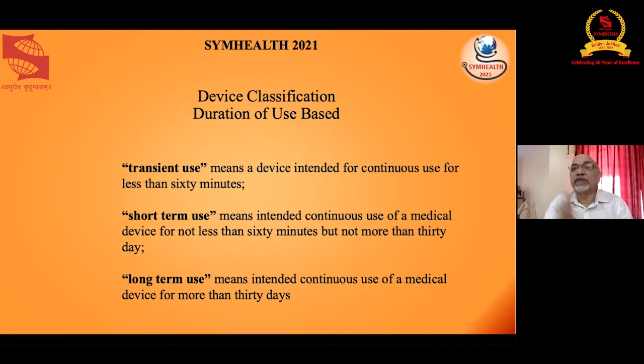A short-term use means more than 60 minutes but less than 30 days. Now, typically, a Ryle's tube which is introduced through the nose into the stomach is a short-term device. You do not keep a Ryle's tube for more than 30 days. Neither do you usually keep a urinary catheter for longer than 30 days. So they're short-term devices. Long-term devices means those devices which are kept in contact with the body or inside the body for more than 30 days. So orthopedic implants, artificial tooth, cardiac stent. Once you're putting the stent, you don't remove it. You don't change the stent every now and then. Actually, you don't change the stent at all. So it is known as a long-term. So classification of devices is based on the risk. It is based on the duration of use, and this is the way.